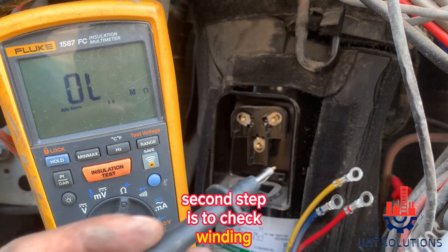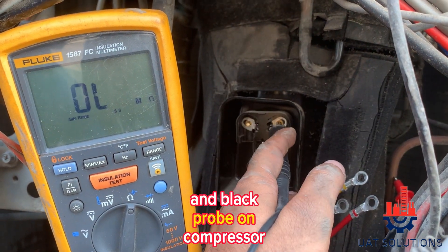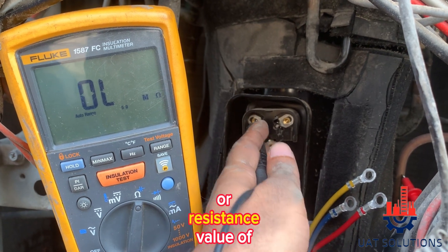The second step is to check winding insulation. Put the red probe on the compressor terminals one by one and the black probe on the compressor discharge pipe. It should show either an open circuit or a resistance value of more than 50 mega ohms. As per the shown results, it's a good compressor.